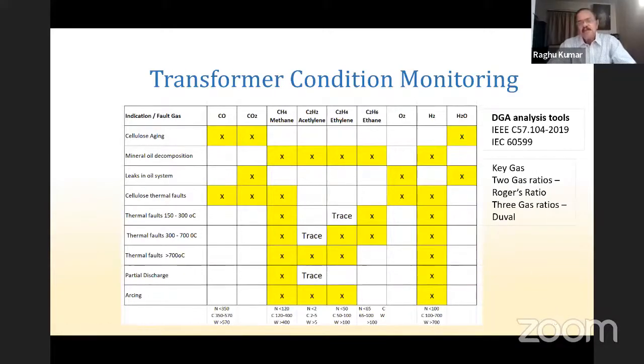IEC and IEEE have relevant standards which give you some tools to find it out. There are three methods basically used. One is called the key gas method, where only a single gas concentration is considered for fault finding. Like in the previous case I showed you, ethylene concentration shows that it is going to be a high temperature fault. Acetylene shows that it is an arcing fault. Things like that are identified from a key gas.